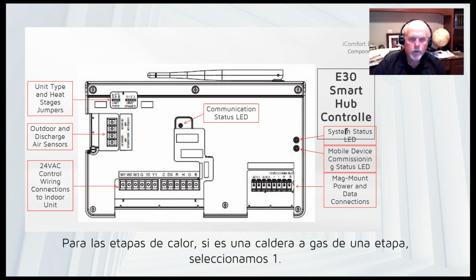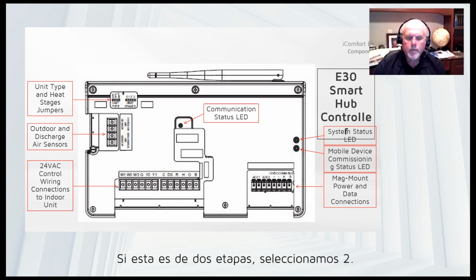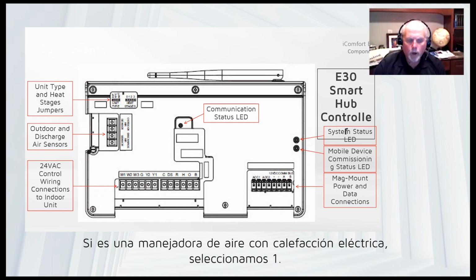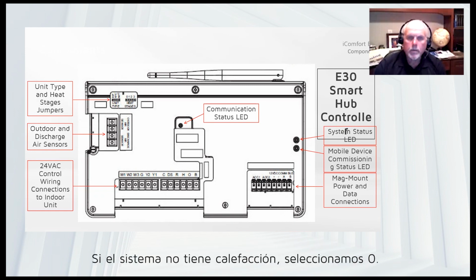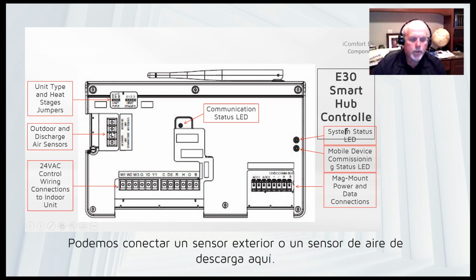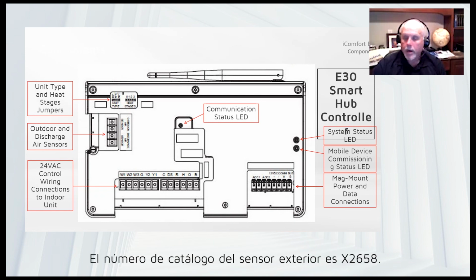Heat stages, again: gas furnace, if it's single stage, it'll be on 1. If it's a 2-stage gas furnace, it'll be on 2. If it's an air handler with electric heat, it'll be on 1. If it's no electric heat, it'll be on 0. We can hook up an outdoor sensor or a discharge air sensor, and this is where that would hook up. The outdoor sensor, and it's not in here, but the catalog number is an X as in X-ray 2658. That would be your outdoor sensor.